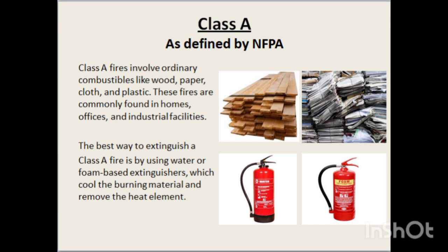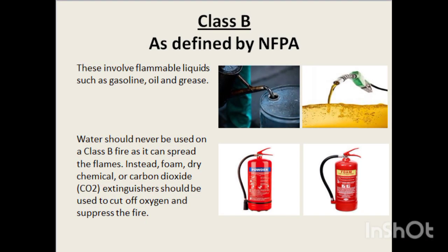Next, we have Class B fires. These involve flammable liquids such as gasoline, oil, grease, and alcohol. Water should never be used on a Class B fire, as it can spread the flames. Instead, foam, dry chemical, or carbon dioxide CO2 extinguishers should be used to cut off oxygen and suppress the fire.